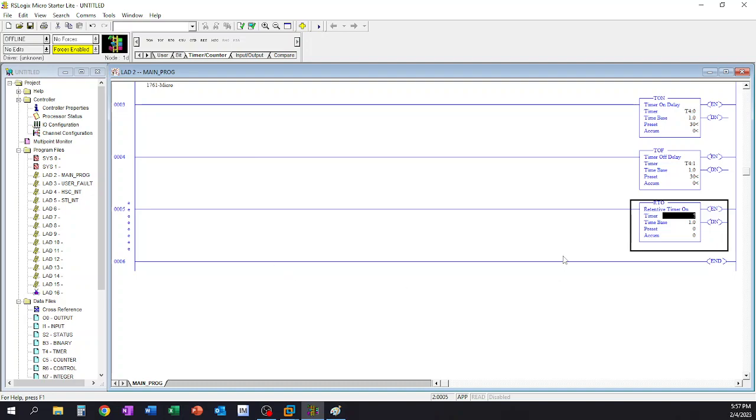Anyway, back to where we were going with this. So retentive timer on, what that actually is doing is it's keeping a time set in from the preset, and it's constantly adding to that time. So if this particular rung were to go false at any given point, then the time that's already been accrued into the accumulation will stay and remain until the feature comes on again or until it's reset.